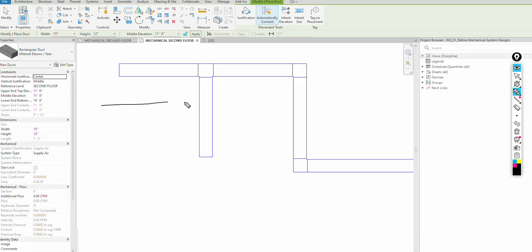Good question. I'm talking about section view. So this is if I'm looking from here. It's happening like this. Instead of cutting the whole duct, that is a T. You cut the hole and put a T there. Instead of doing that, we will make a hole in the main duct and insert a collar. This is called a tap. And then from this one you can get your outlet. You will see it in a minute. Now I show you in 3D in Revit. I hope it is clear now.